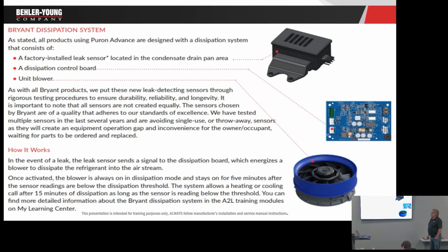Okay, so we're going to have something called a dissipation system. The industry calls it a mitigation system, but Bryant and Carrier call it dissipation, okay, because they have to be different. So what exactly does this do? So remember that lower flammability limit? Even though we can't ignite it except with a flame, until we get to the lower flammability limit, it won't ignite. So we never want to let it get there, okay, as a precaution.